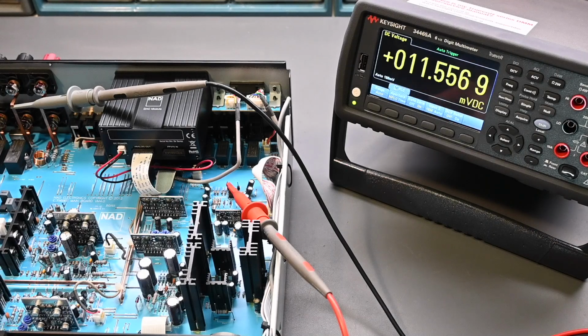Keep in mind that line voltage variations will also affect the readings. If the line voltage changes, the idle current changes, and then this idling point of the ISC circuit will change as well. So you kind of want an average - that's what it really looks like. They don't give a range, they just say make them equal, but in reality I think it means make it as close as practical, since they're never going to stay exactly equal.